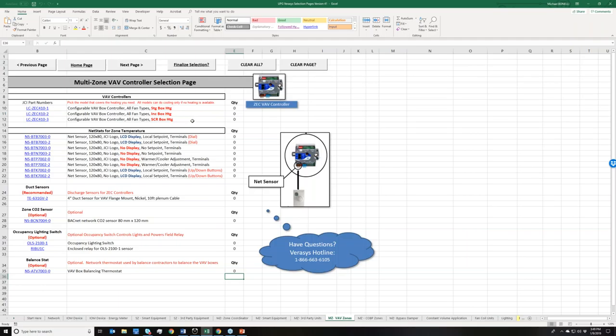It's going to modulate the damper based off of flow. What you could do if you had a zone damper is retrofit it with cross flow pickup tubes and turn it into a VAV box with no fan. But as it stands right now, we do not have a zone damper controller that is standalone.